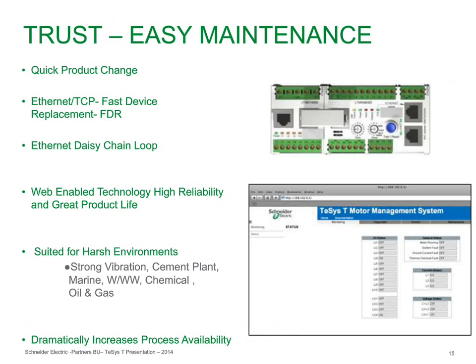Now, when it comes to maintenance, you say, okay, I have a device here that can be installed. It would give me intelligence for my motor control centers, but how easy is this to maintain? I'm going to tell you it's fairly easy. We do have some health circuits in there that will actually tell you over the network, is the unit working properly? Is it wired properly? It'll even tell you, like I said, if wires are mislabeled, it will detect that.